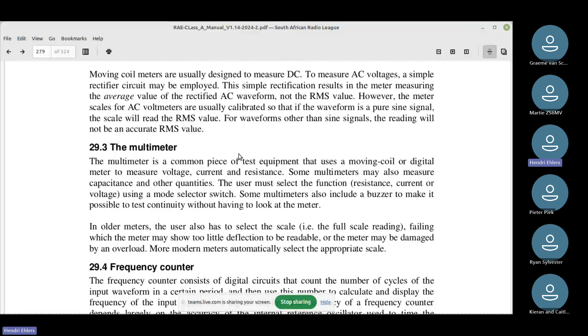Some of the meters you get, most analog meters, you have to select the scale. And if you select a scale that's too low, you're going to overdrive the meter and it can be damaged. Then you get the digital meter, where you've also got to select the scale, which can also get damaged if you use a scale too low. And then you get a meter, what they call auto ranging, which will automatically adjust the display until it gets to the right resolution, so it gives you a proper reading.